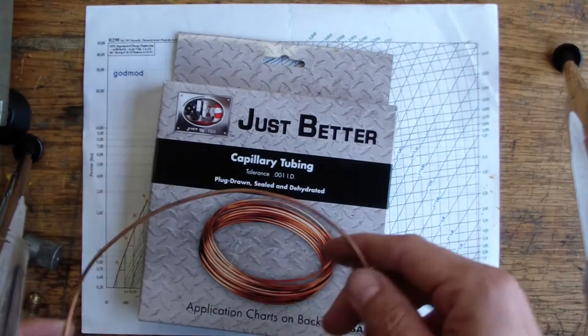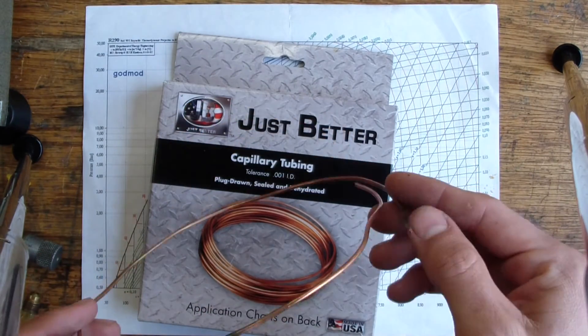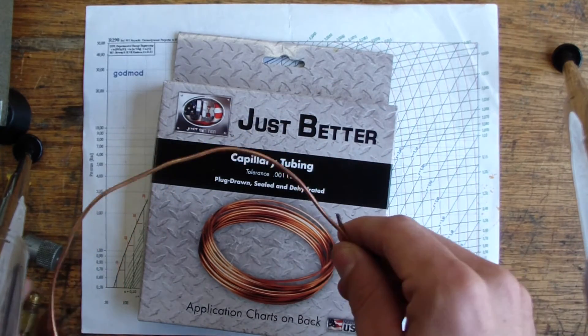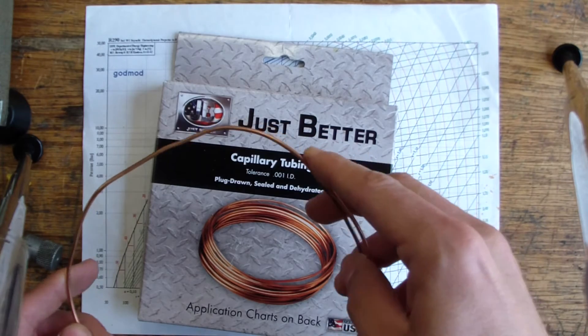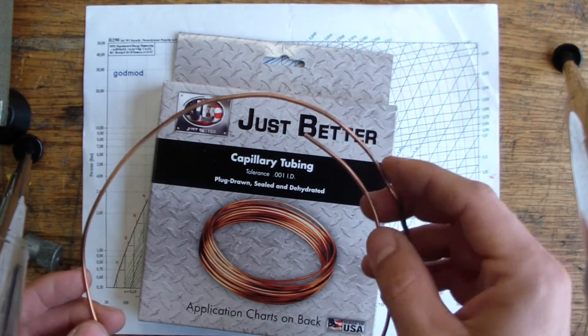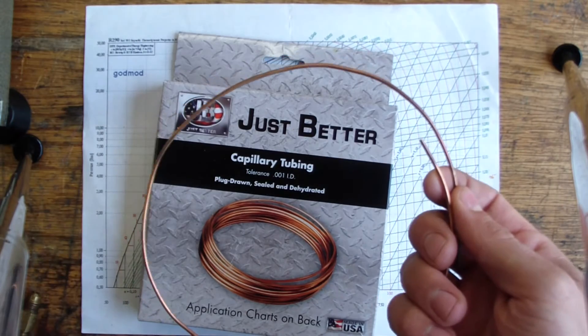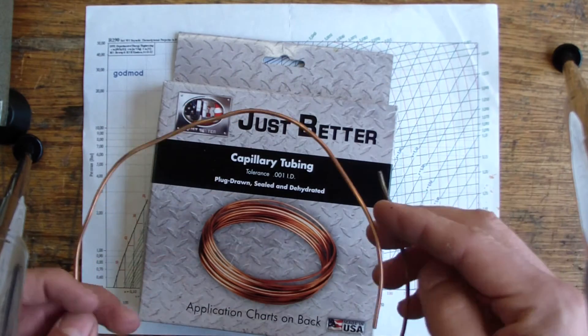So in a well designed system where the capillary tube is the right length, the heat exchangers and the capillary and the compressor are reasonably well matched, capillary tube has the ability to regulate sub cooling to a certain extent and keep the evaporator well fed.